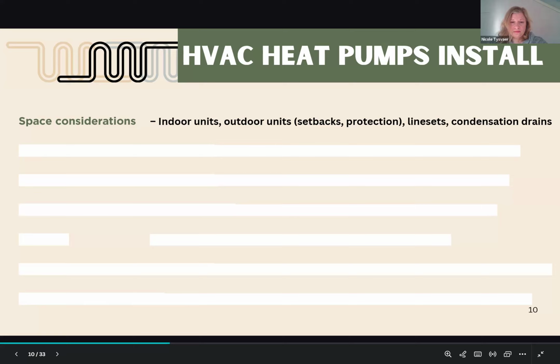Now, you also want to make sure on the outdoor units, it's recommended that you have some kind of cover over your unit to get optimum performance. It's not necessary, but whenever possible it's good to have an overhead cover for your outdoor units. You want to make sure you look at the codes because there are setbacks on outdoor units, so you don't want to be too close to the property line and have an issue there. And you want to plan for your line set and your condensation drain exits and entrances to make sure all that works in the best way possible with the conditions you're under.